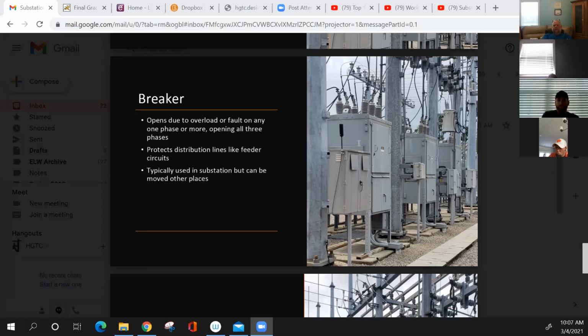If the fault is still on it, it'll trip again and stay out for about 10 seconds, then come back on. If the fault's still there, it'll operate again and trip out again. I think that's another 15 or 20 seconds, depending on who sets up the breaker and the times that it operates. If the fault is on it a last time when it comes back on, the breaker will operate, open, and clear itself right there until the fault is cleared. At that point, you'll have to go out, patrol the line, find the fault, clear it, and then dispatch can re-energize that breaker. But that is a substation breaker.